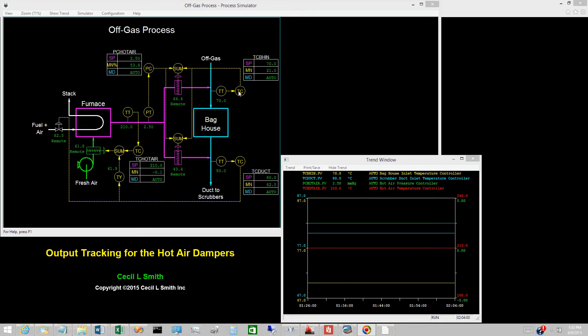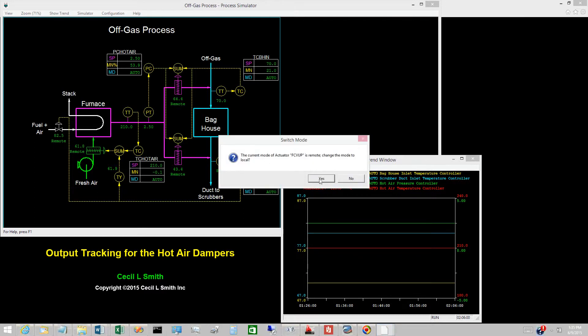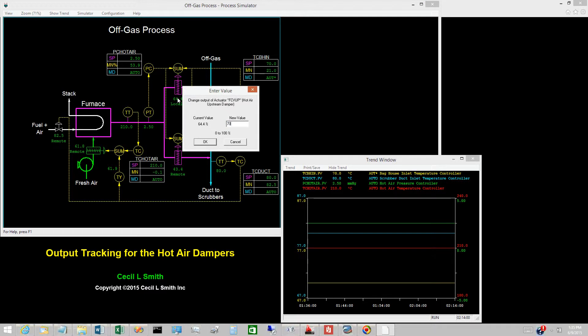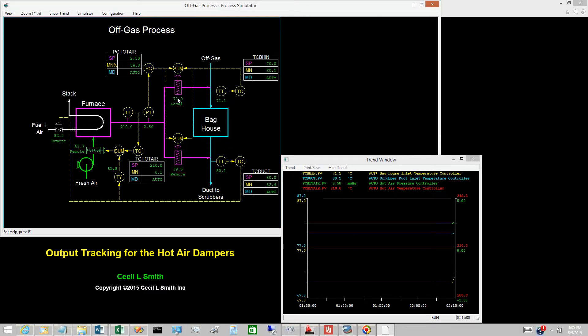To illustrate the effect of tracking, switch the hot air damper to baghouse inlet to local. The mode of the baghouse inlet temperature controller is displayed as AUT*, so tracking is active. The mode of the hot air pressure controller is auto, so this loop is functioning. Change the opening of the hot air damper to baghouse inlet from 64.4% to 70%. To maintain the same arithmetic average, the opening of the hot air damper to scrubber duct inlet changes by the same amount but in the opposite direction.